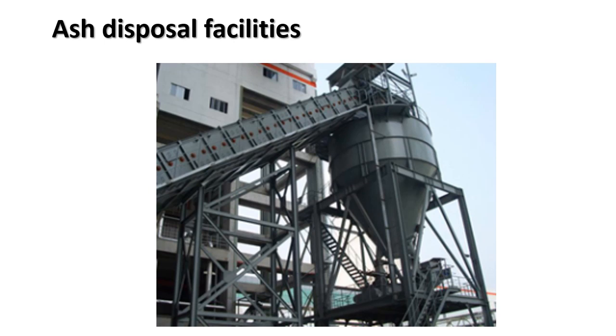Next factor is ash disposal facilities. Ash produced after burning coal is about 20 to 40% of the weight, that is 1500 to 2000 tons per day. This becomes a serious problem as it comes out in hot condition and is highly corrosive. Therefore, there must be sufficient space available for disposal of large quantities of ash. The ash from the power plant is also used for many industrial processes, so the disposal problem does not arise as severely.